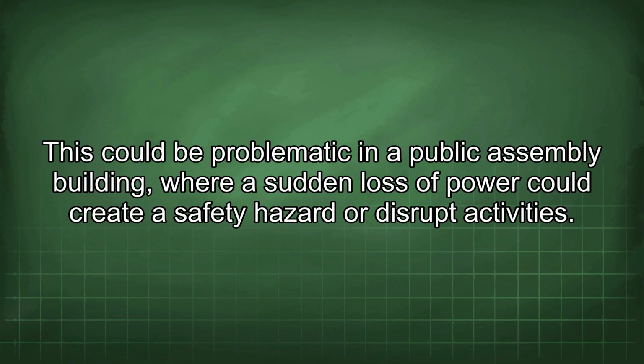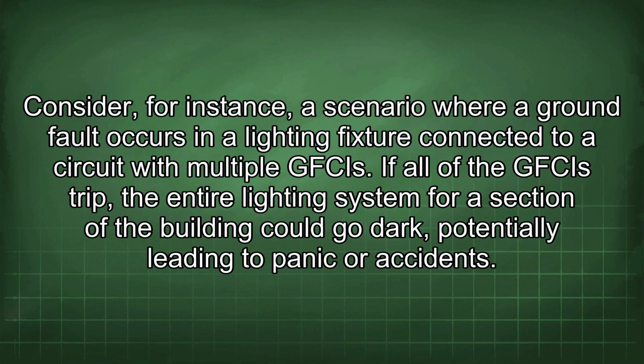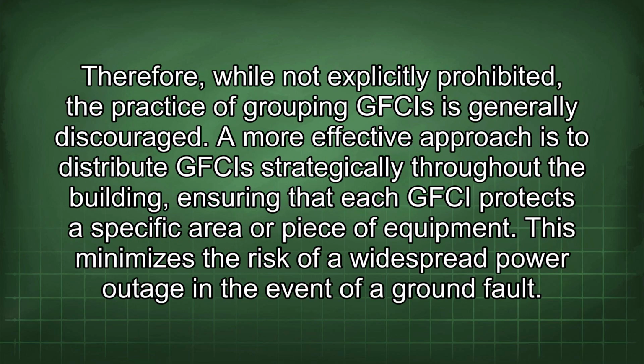This could be problematic in a public assembly building, where a sudden loss of power could create a safety hazard or disrupt activities. Consider, for instance, a scenario where a ground fault occurs in a lighting fixture connected to a circuit with multiple GFCIs. If all of the GFCIs trip, the entire lighting system for a section of the building could go dark, potentially leading to panic or accidents. Therefore, while not explicitly prohibited, the practice of grouping GFCIs is generally discouraged.